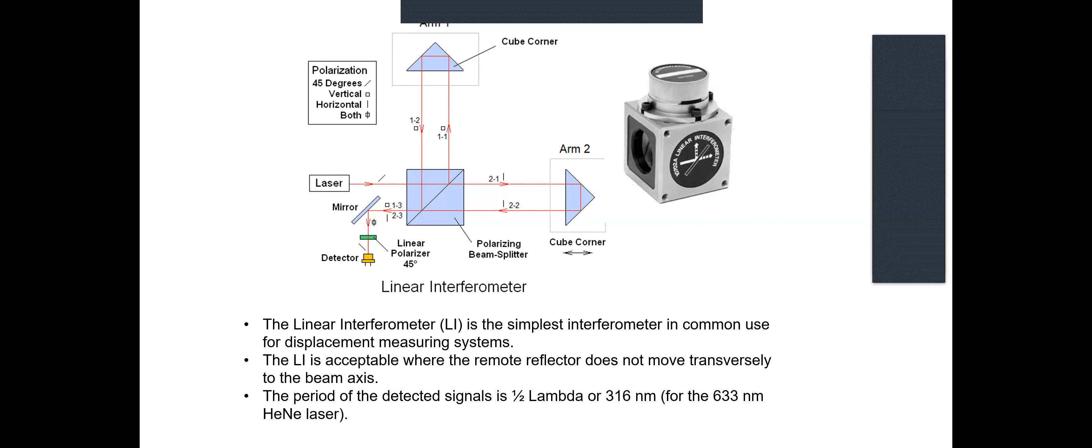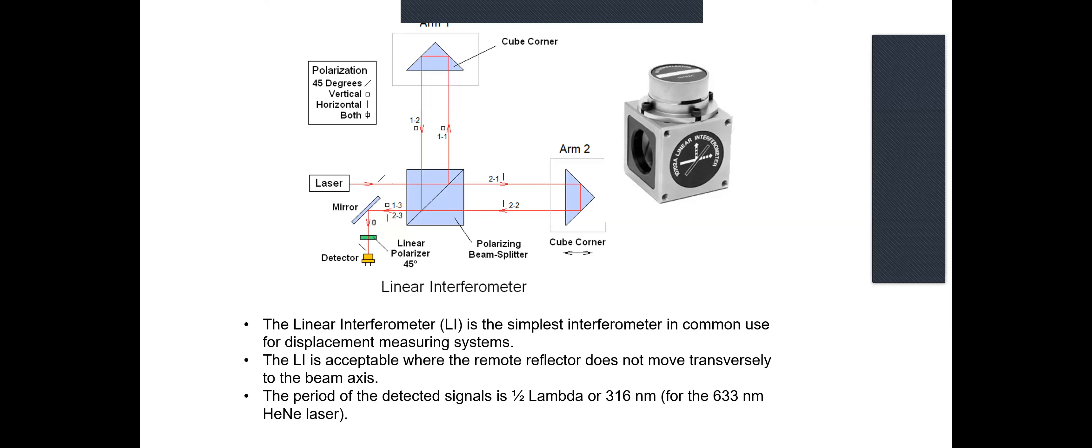The sensitivity or the resolution of the linear interferometer is 316 nanometers using the HeNe laser. And just as a digression, the HeNe laser is unique. It was the second laser, I believe, that was ever invented, but 60 some years later, it's still the absolute best laser for use in a metrology interferometer because the optical frequency corresponding to wavelength is accurate to many, many orders of magnitude. And that's not true of most other lasers. In fact, there is no existing replacement for the HeNe laser that would do the job as well for an affordable price, and almost at any price. A laser pointer just won't do it.